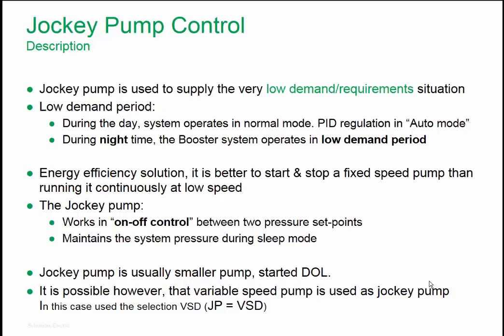Jockey Pump Control is used in situations when there is a low demand for water consumption, in applications with booster control or with PID regulation in general. For example, during the day, the whole system operates in normal mode and PID regulation is working in automatic mode. During the night, when there is low demand for water, it is more efficient to start and stop a fixed pump than to operate the main pump at low speed.